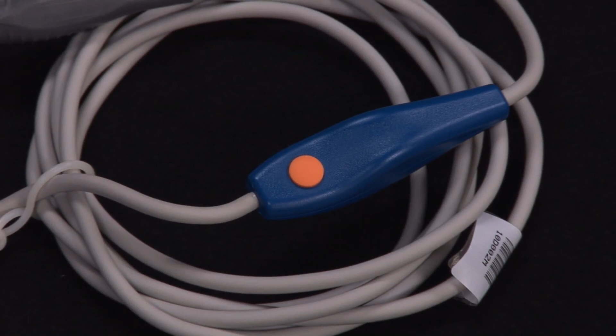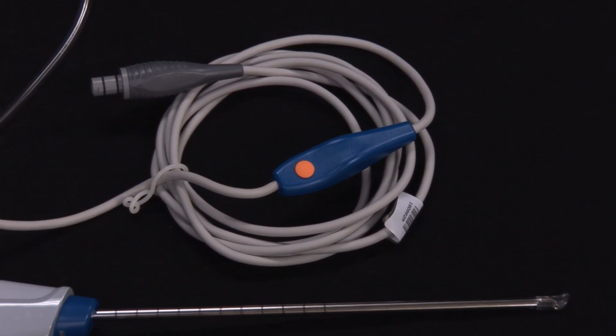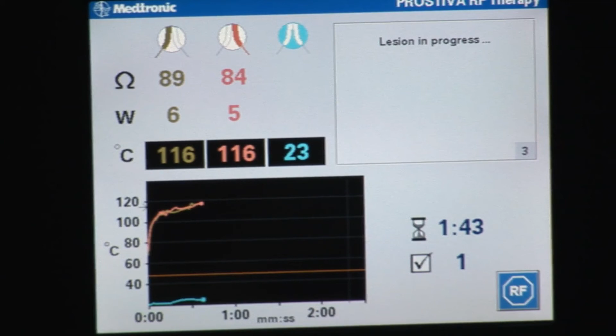Start the radiofrequency power delivery by pressing and releasing the orange on-off switch on the handpiece cable. The switch functions only as a press and release switch and is not designed to be held in the press-down position. Confirm that the lesion in progress appears and is monitoring output on the screen display. The lesion time is automatically set for 2 minutes and 20 seconds.